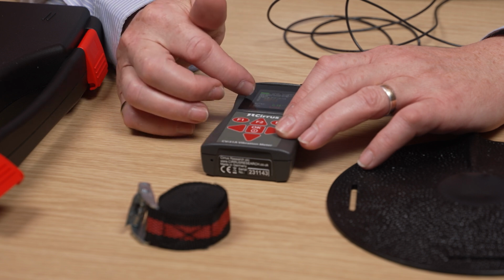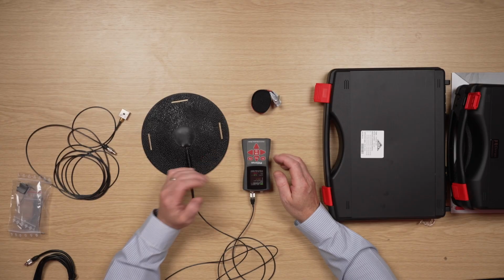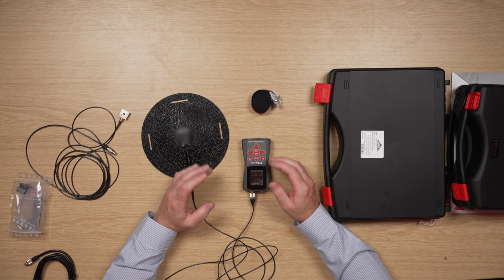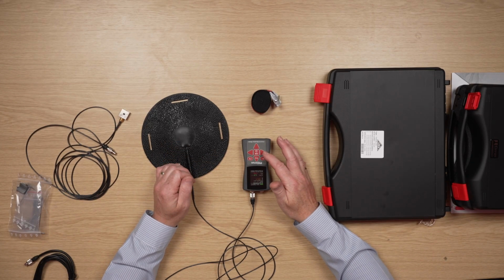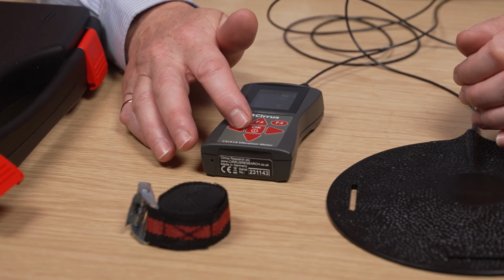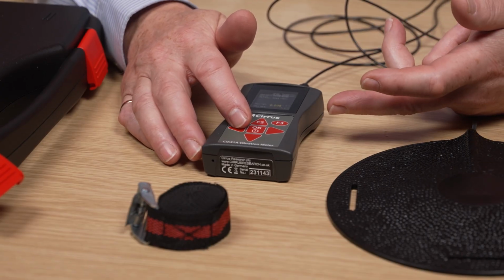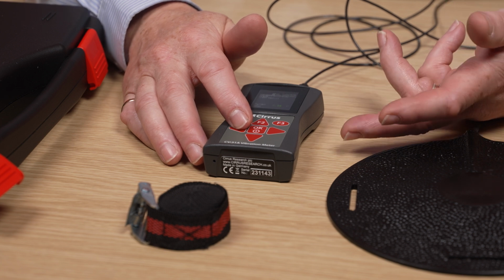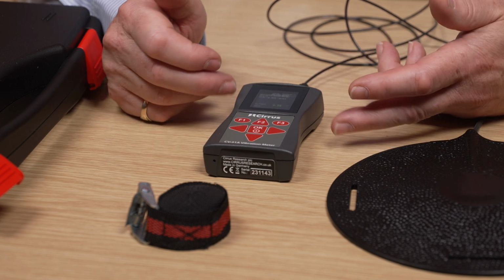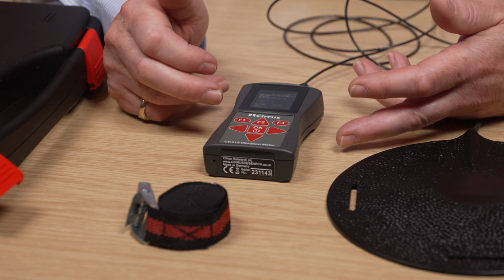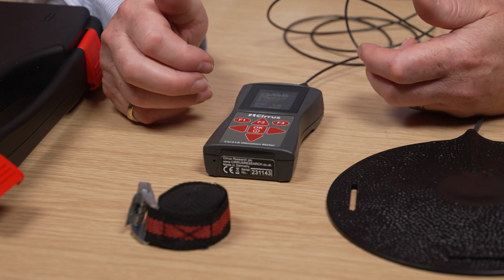We've got it in acceleration terms at the moment, but you can have it in vibration dose value, and you can also look at the crest factor with this by just pressing the left arrow on the key here. You can take it through where you've got vibration dose value, or you've got the crest factor, or go back to what they call the RMS values, which is basically the acceleration, as we've seen before. So to take a measurement with this, it's exactly the same.